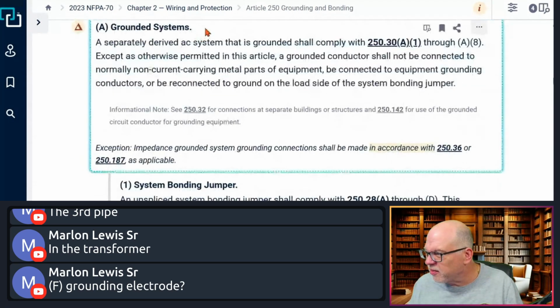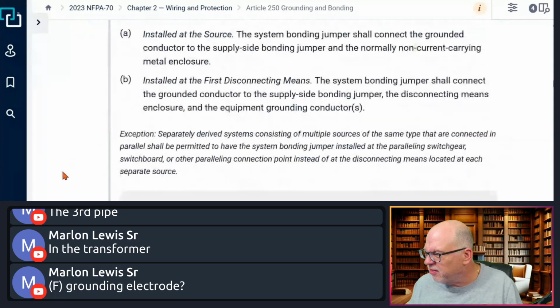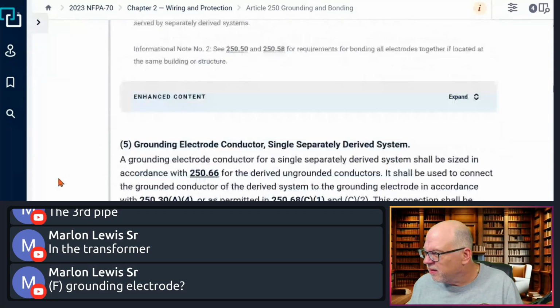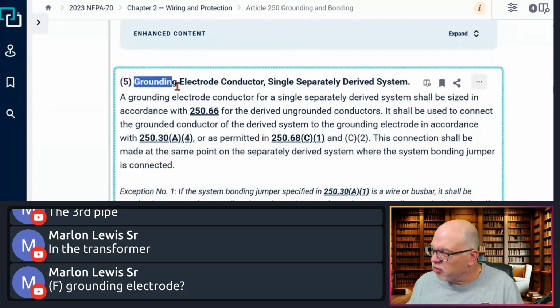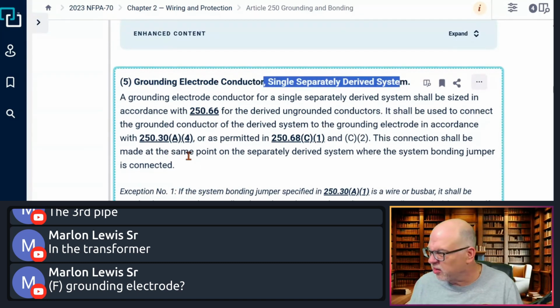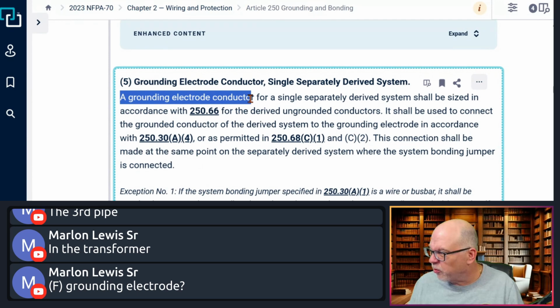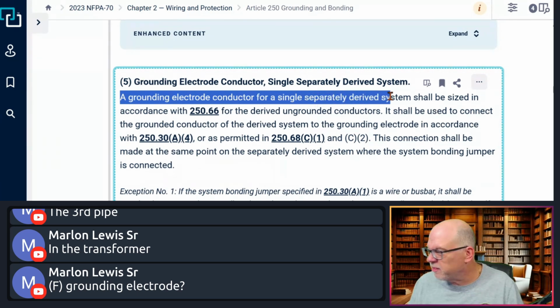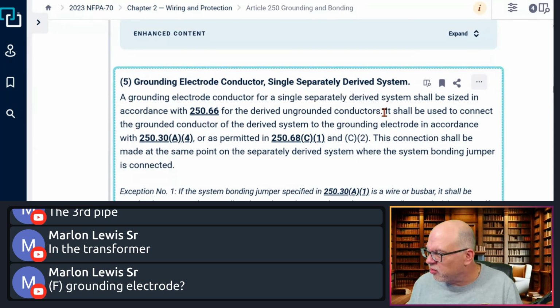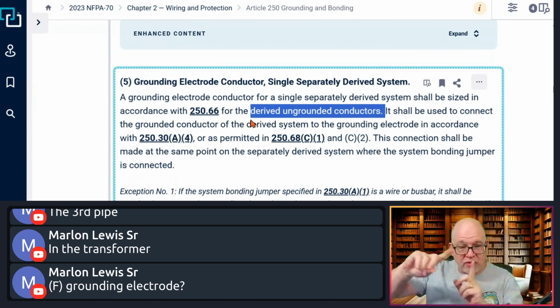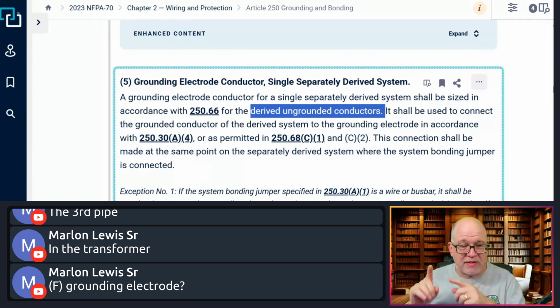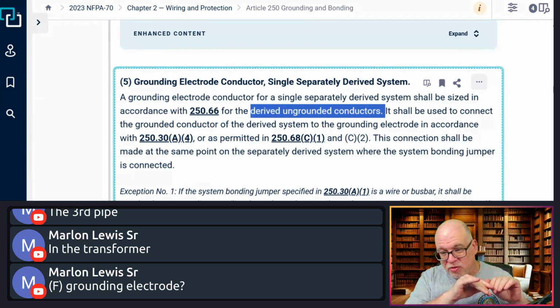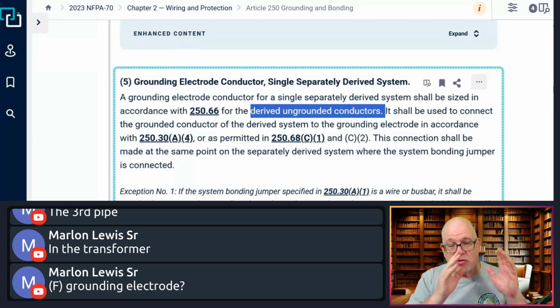So here's a grounded system. Let's go to A5. Okay, there you go. Grounding electrode conductor, and it says single separately derived system. So here are the exceptions, but let's look at the rule. It says a grounding electrode conductor for a single separately derived system, a transformer in our case, shall be sized in accordance with 250.66 for the derived ungrounded conductors. So we know we're using the secondary conductors to size it. So we're going to use 250.66. In that table, it has conductors on the left side. What do we use? We use those derived conductors.